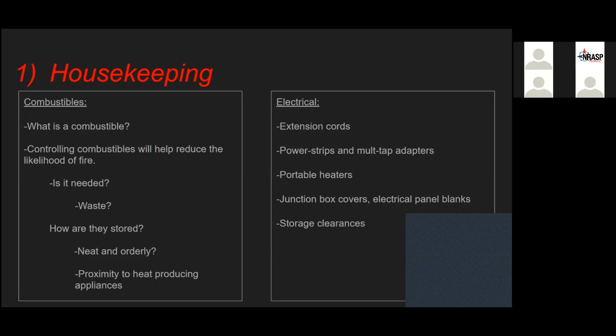Extension cords should never be used as permanent wiring. In the fire code's eyes, permanent wiring is anything over 90 days. They should never go through a wall, through a ceiling, through a doorway, under a rug. Those are all violations of fire code and have a way of contributing to starting a fire. You have the potential to compromise the cord, pinch the cord, compromise the insulation, and now we have a source of heat for our fire to begin.